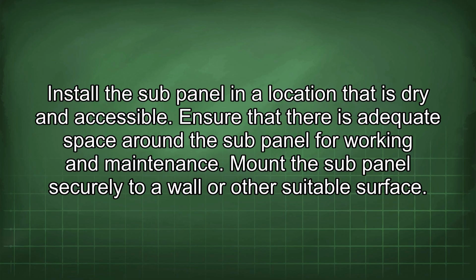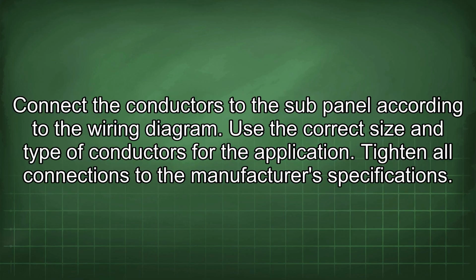Install the sub-panel in a location that is dry and accessible. Ensure that there is adequate space around the sub-panel for working and maintenance. Mount the sub-panel securely to a wall or other suitable surface. Connect the conductors to the sub-panel according to the wiring diagram. Use the correct size and type of conductors for the application. Tighten all connections to the manufacturer's specifications.